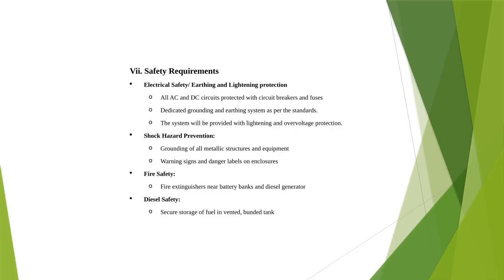For shock hazard prevention, grounding will be done for all metallic structures and equipment. We are also going to have some warning signs and danger labels on all enclosures. For fire safety, we are going to have fire extinguishers near the battery banks and also the diesel generator. For diesel safety, our diesel will be secured in a vented area.